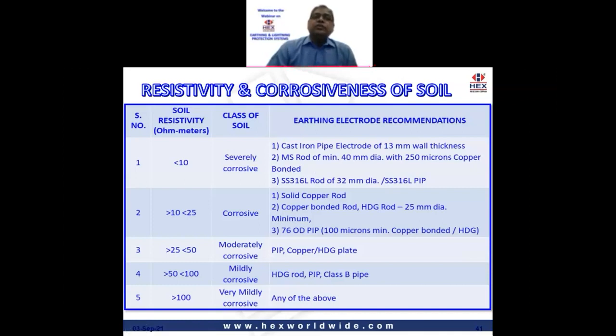Therefore, for severely corrosive soil conditions such as these, we recommend a CI or cast iron pipe electrode of at least 13 mm wall thickness, or a 250 microns copper bonded earth rod of 40 mm diameter minimum. Of course, for acidic or marine soil conditions, SS316L is the best bet. So we have even supplied a pipe-in-pipe in SS316L, which has given a very, very long life where they have been installed.